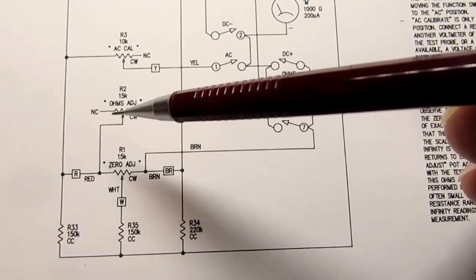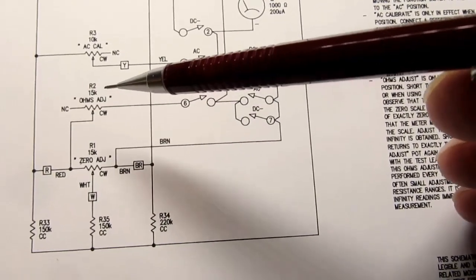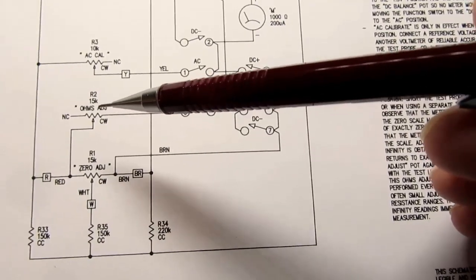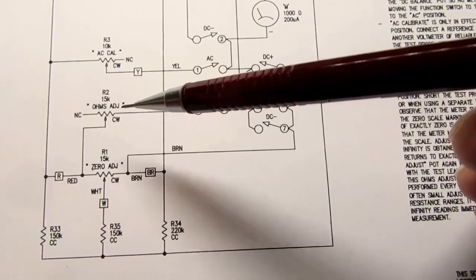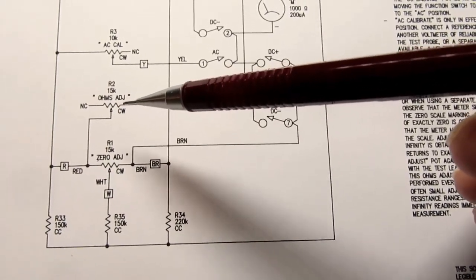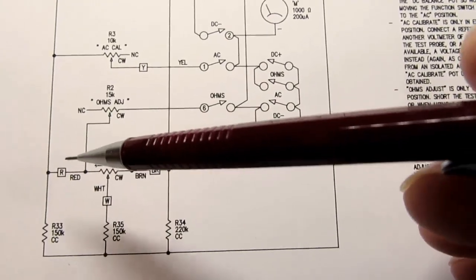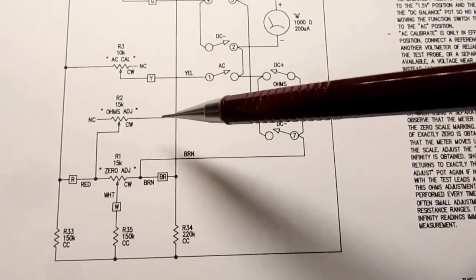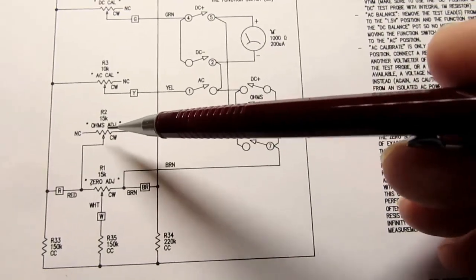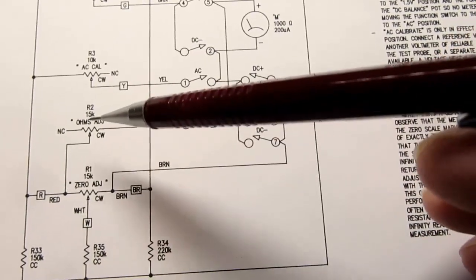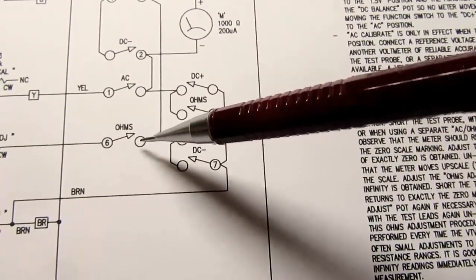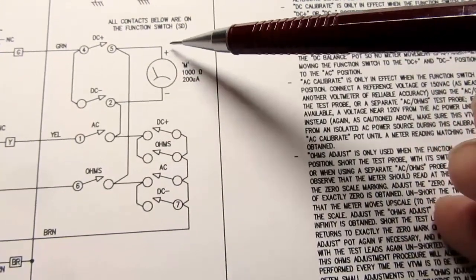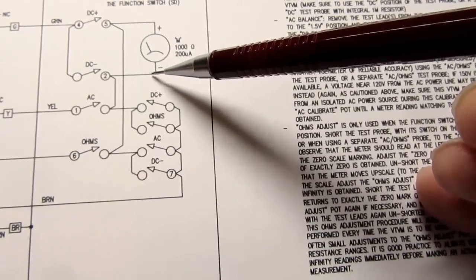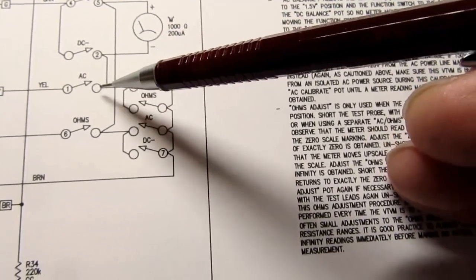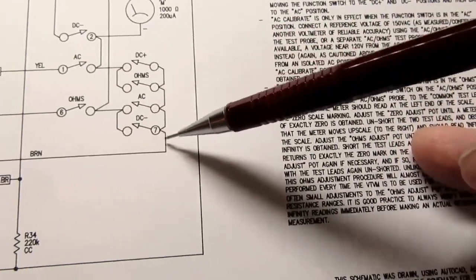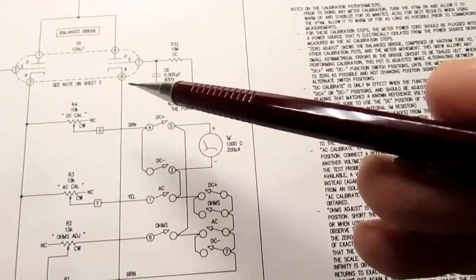And of course it has its own calibration pot. But we don't call it a calibration pot here. It's a front panel control. It's not something you set only during meter calibration. It's something that's a working adjustment that has to be frequently adjusted. But electrically it's doing exactly the same thing. It's going from this side of the bridge to this side of the bridge via this resistor and the meter movement. So we go through the ohms adjust pot, we go through a contact that's closed in the ohms position, we go up here, we go through into the plus side of the meter movement, and then out the minus side, and we have to find a contact that's closed in ohms, and that's this one, and that brings us back to the right side of the bridge.